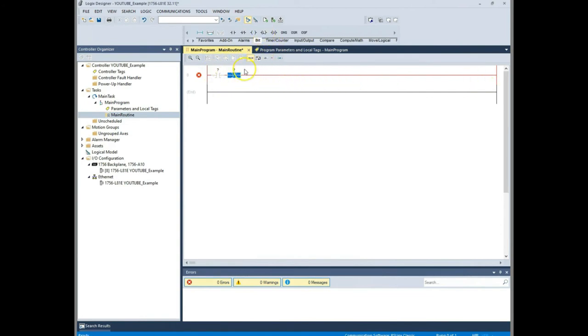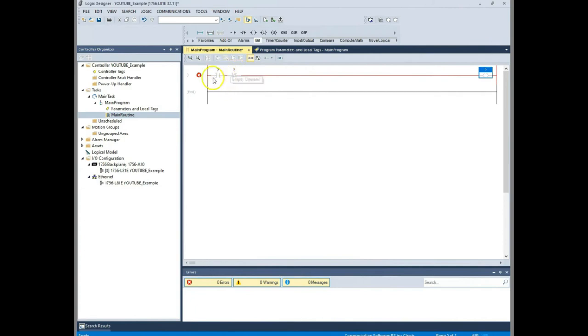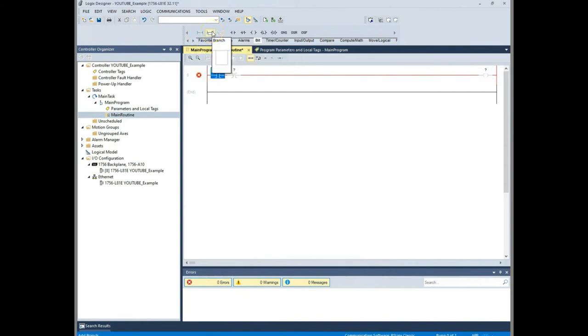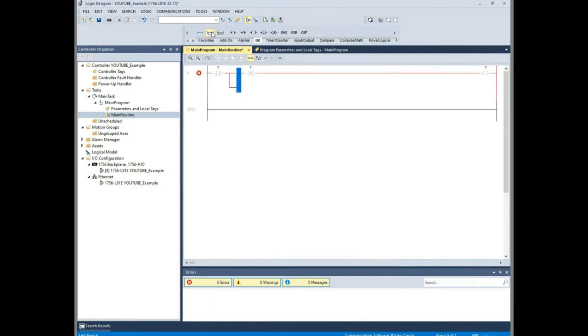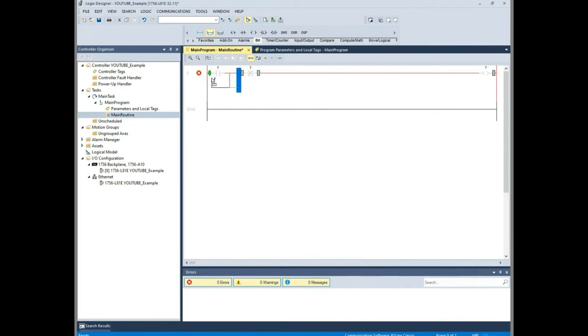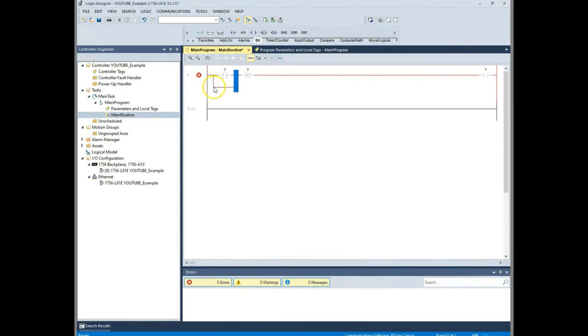Now what we need to do is add our OTE or our output coil. So we just click OTE and we add it to this line here. Finally what we need to do is, if you remember from our diagram, we had a contact that's associated with our coil in parallel around our start. And so in order to do this we're going to click our start and then we're going to go to the second option here which is called branch. And when I click this it brings a branch down. It's kind of aggravating how it places this sometimes but you notice this dark blue line here. If I click that and hold it I can move it wherever I want to move it. So I can either branch around my start or my stop however I want to. But I want to branch around my start here so I'm going to let go of that. And you see now I've got a parallel path around my start button. I want to click on the corner of that and I want to add another XIC here. Okay so this is our circuit.